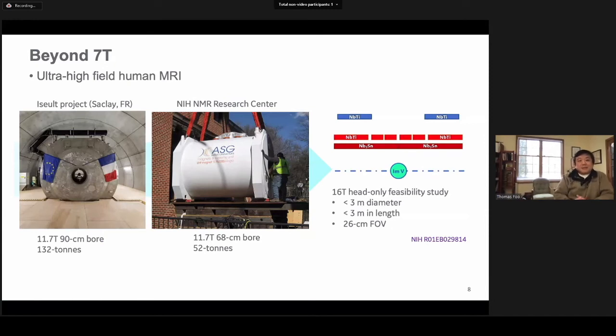Beyond 7T, there have been some excellent systems that have been built, for example the 11.7T whole body system at NeuroSpin in Saclay, France, from Denis Le Bihan's group, and also the NIH 11.7T 68 centimeter bore scanner, but that is actually at 52 tons. We're looking at the feasibility of building a 16 Tesla head-only system using a combination of niobium titanium and niobium-3 tin superconducting wire. This would have a significantly smaller size, but we are targeting imaging only over a 26 centimeter field of view.